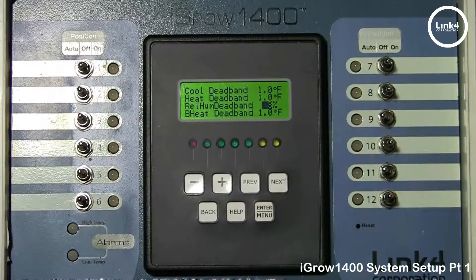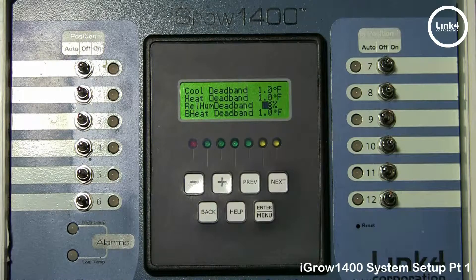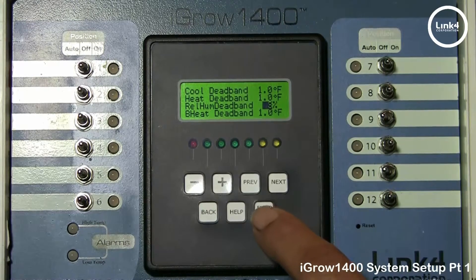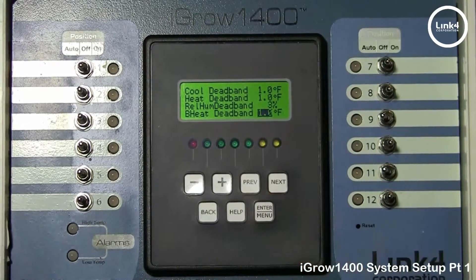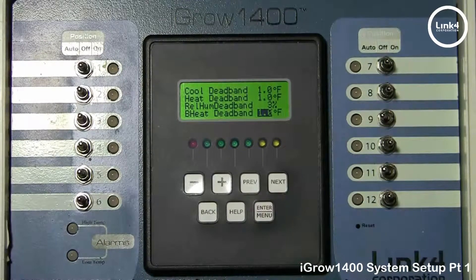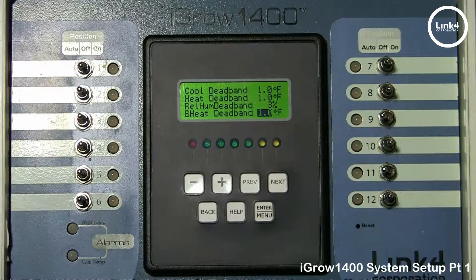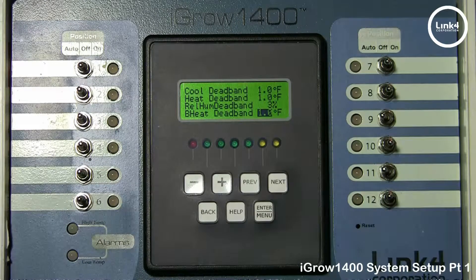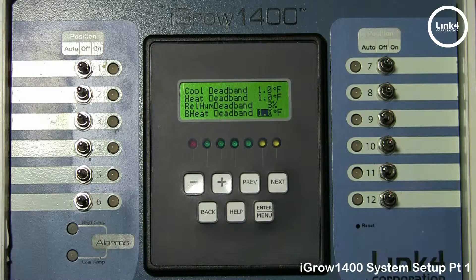The relative humidity dead band is the percentage humidity must drop below the dehumidification threshold before exiting the dehumidification state, and vice versa with humidity. The bottom heat dead band is the number of degrees that the bottom heat temperature must rise above the bottom heat temperature set point or threshold before the heat valve switches off. Typical values might be one degree Fahrenheit or less.